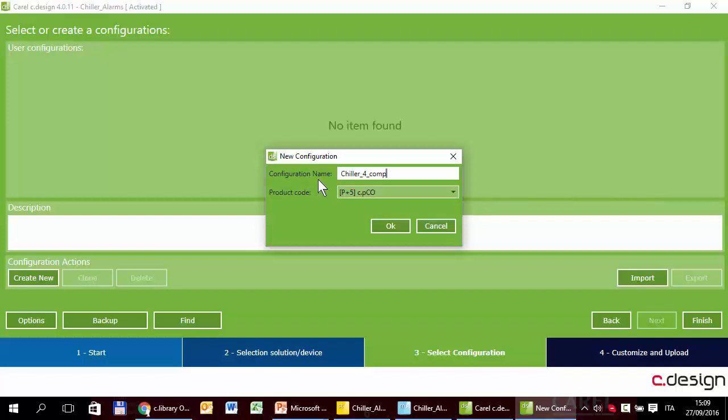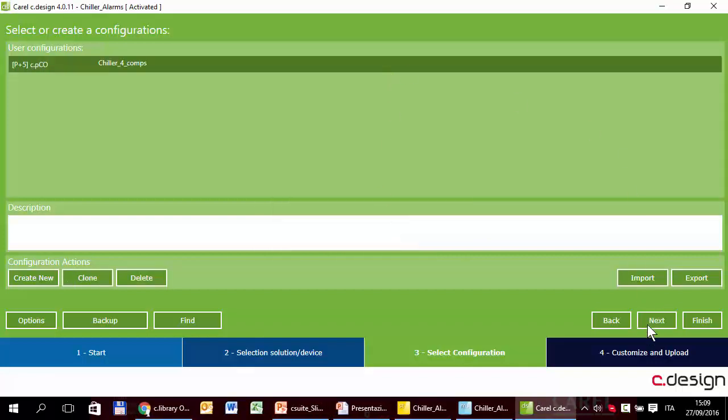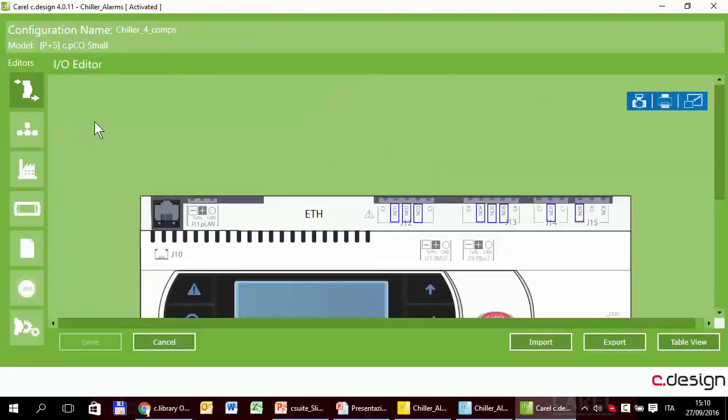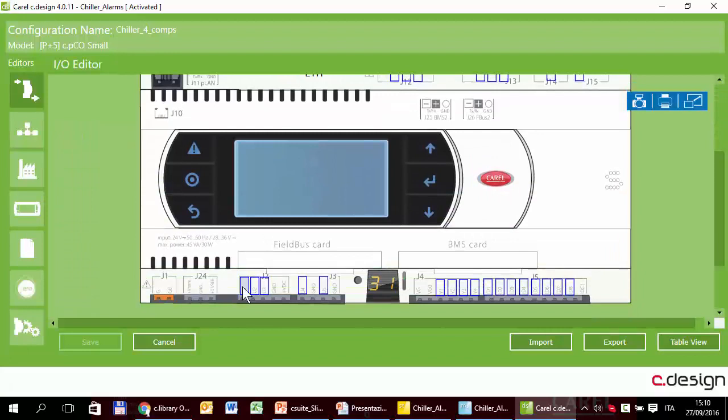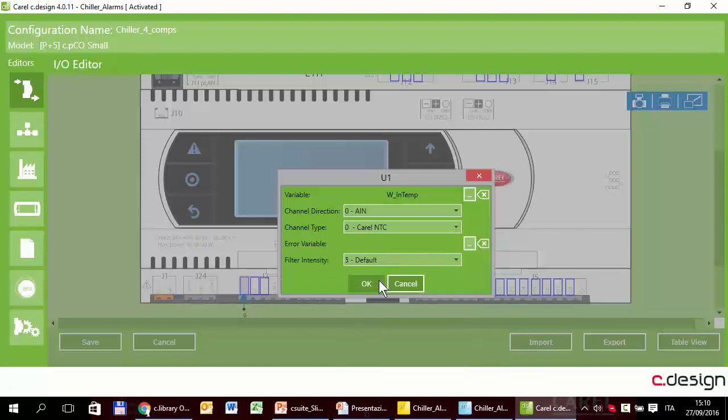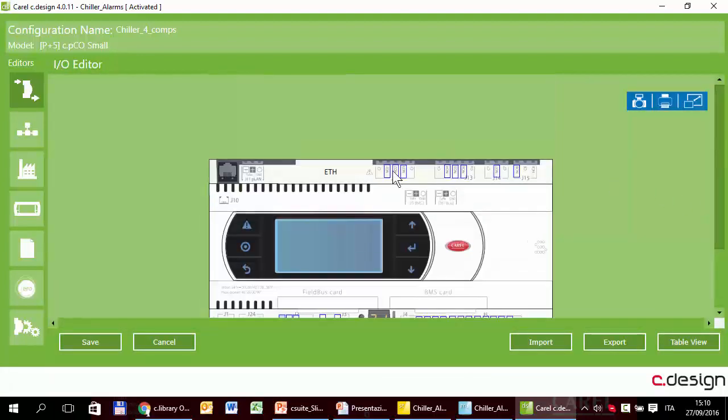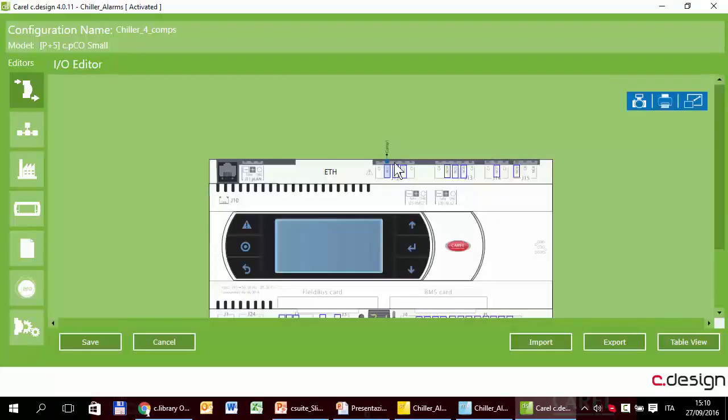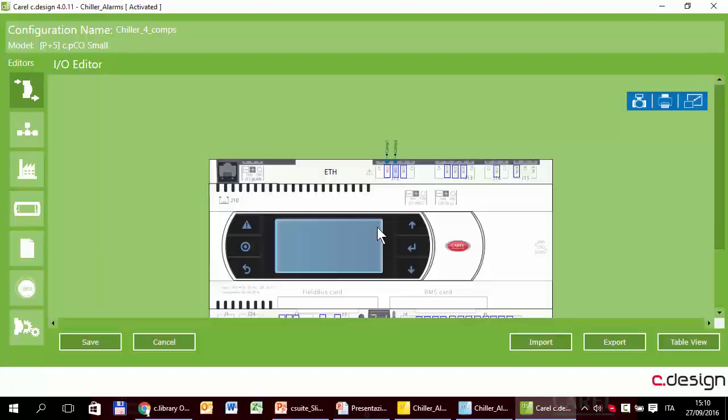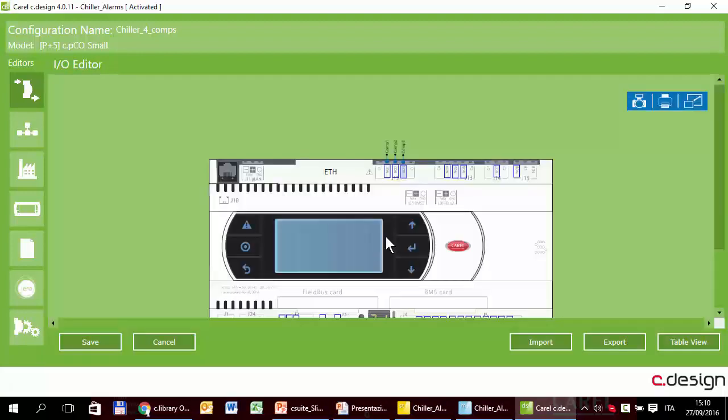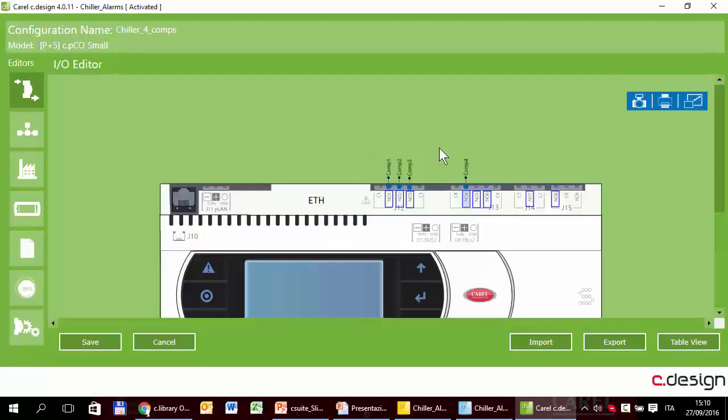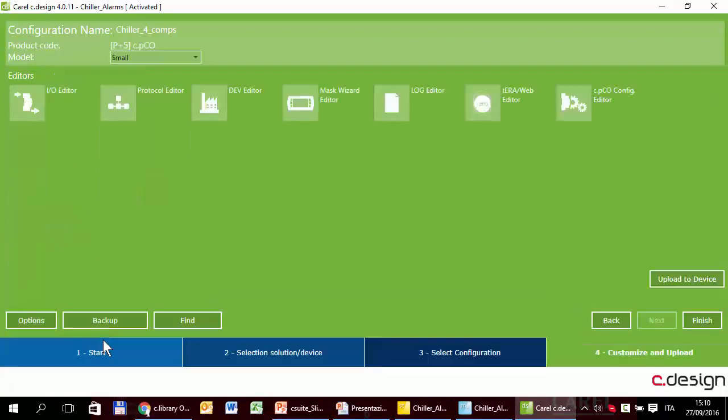Chiller4Comp. In the chiller application we have created two configurations, Chiller2Comp and chiller4Comp. Now, just to speed up the exercise, I will create just one, the one for four compressors. Here is. Next. Input-output. U1 is temperature. It is an analog input. NTC sensor. Here is. In the other side we have compressor 1, compressor 2, 3, 4.